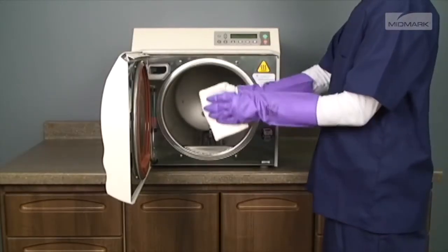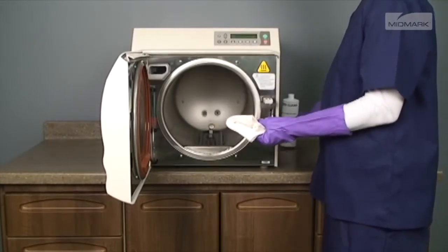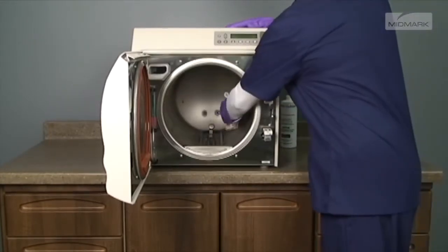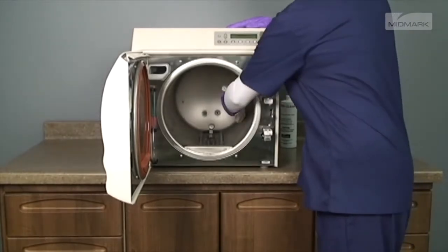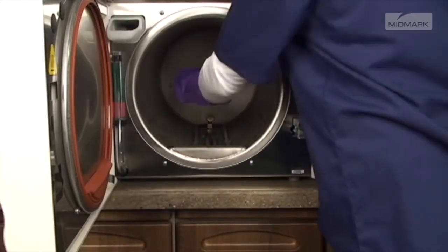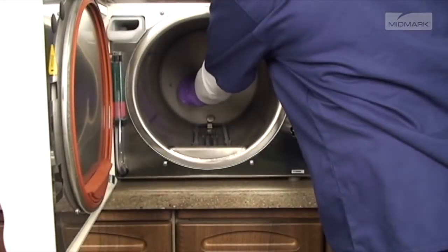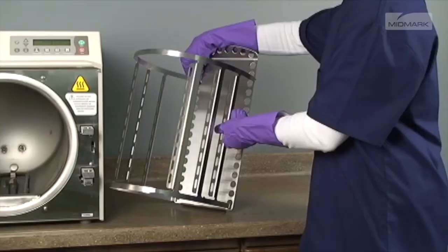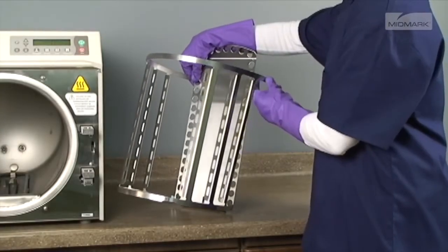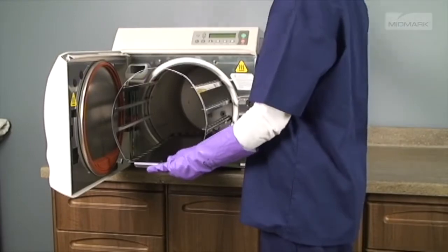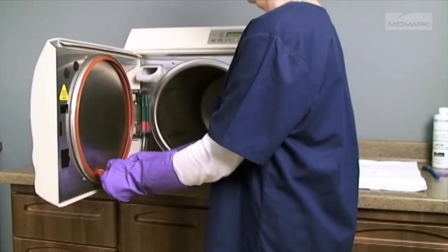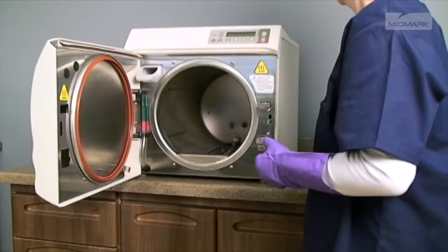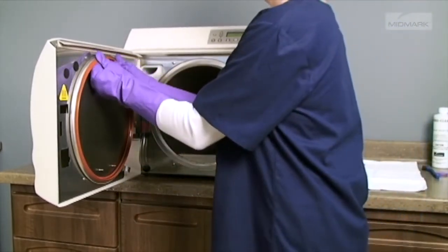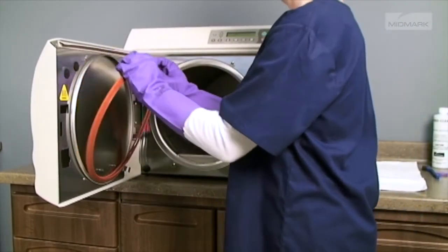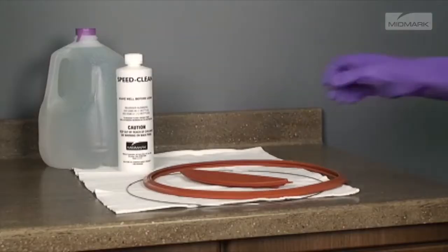Wipe the inside of the autoclave chamber, being careful not to damage the heating element, steam temperature probe, or water level sensor. Reinsert the filters into the appropriate holes by pushing downward while twisting slightly. Reinstall the tray rack. Next, remove and clean the door and door dam gaskets. Remove the door dam gasket, door gasket, and then the gasket ring from the unit.